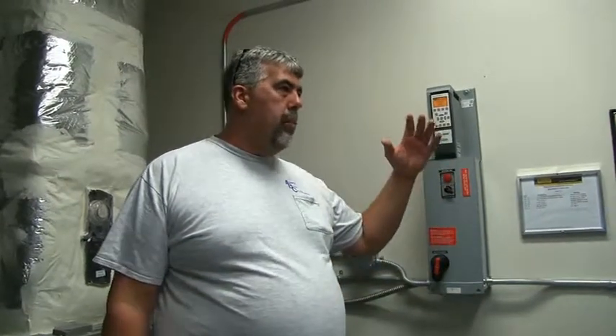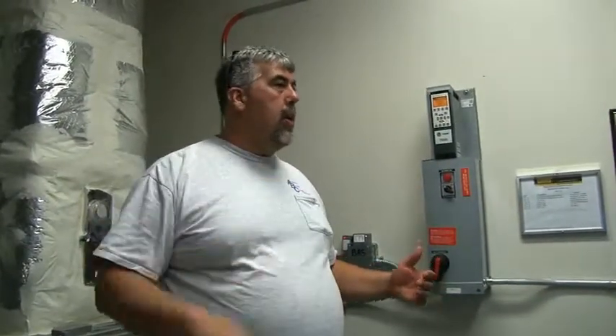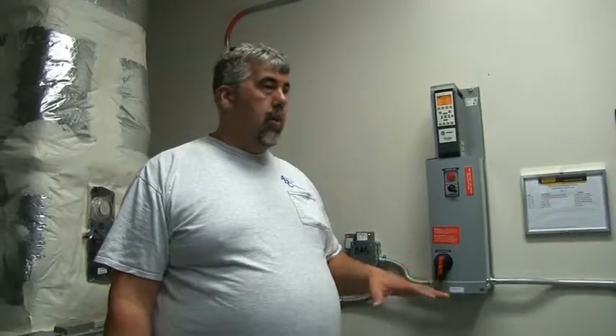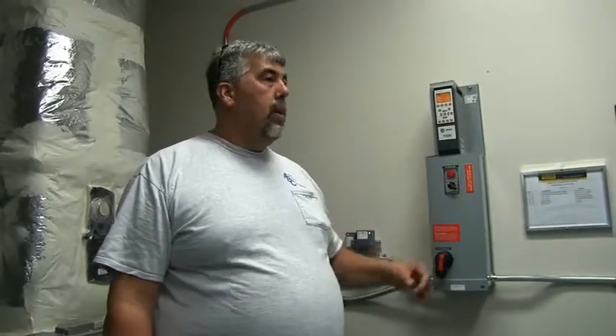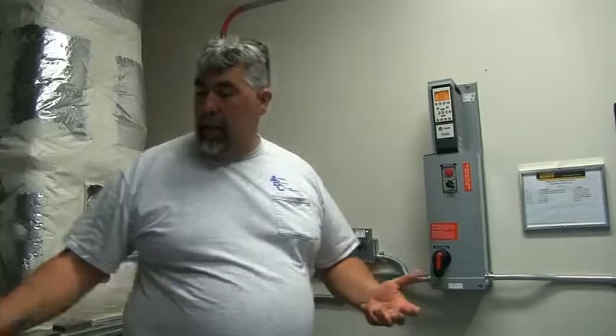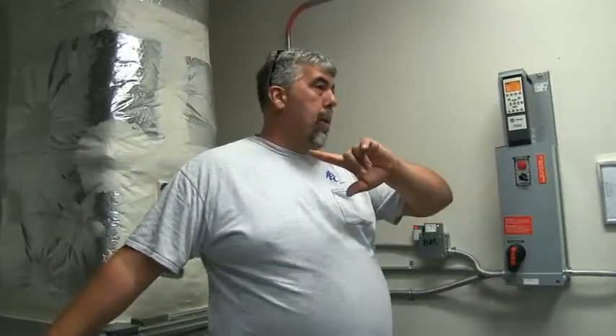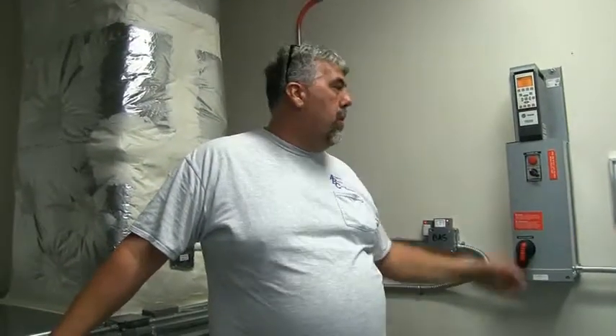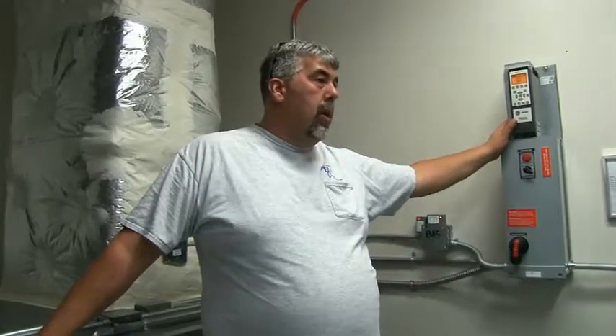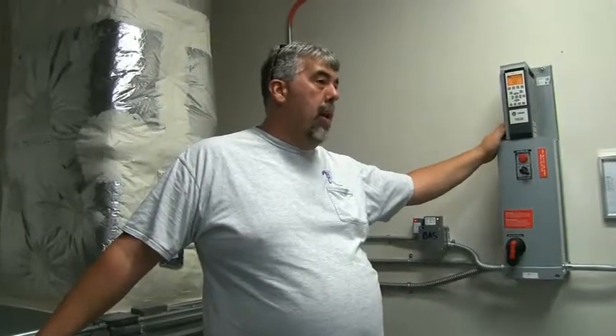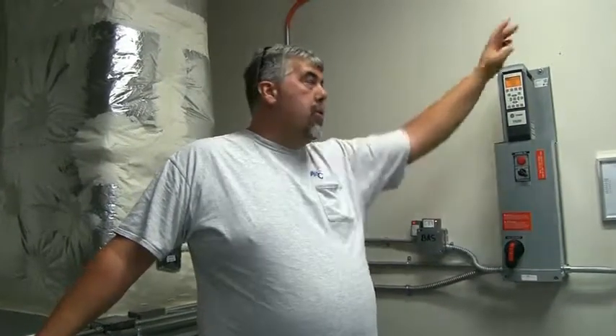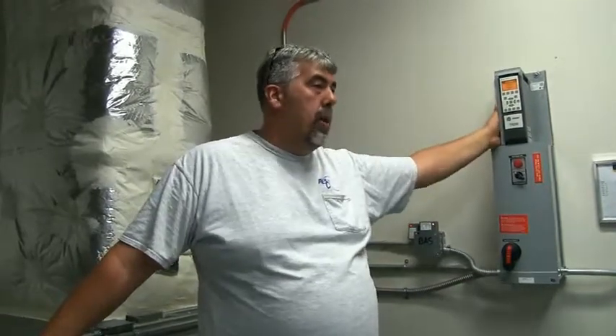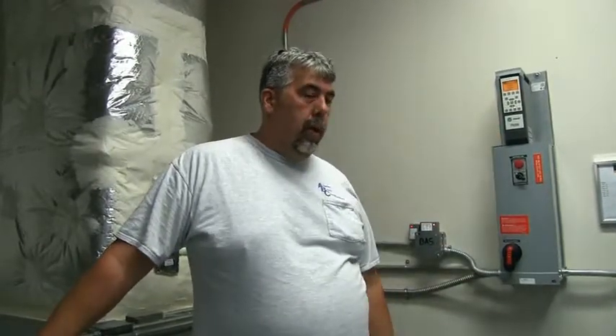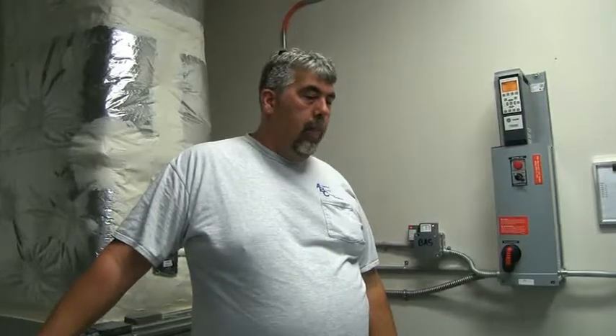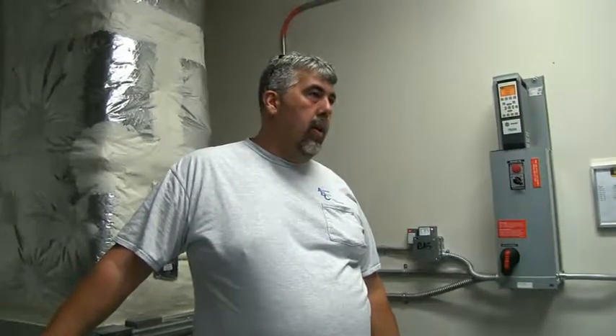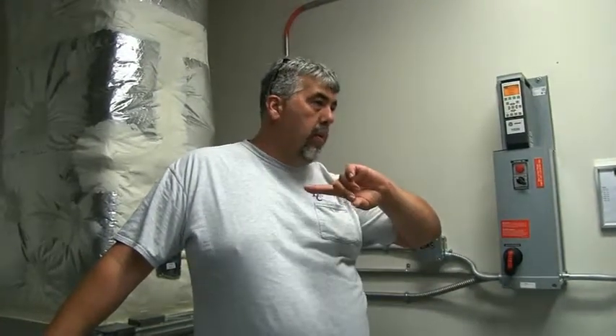I'm still shy a little bit. If the static pressure reset came down or whatever, then it'll start to look at that differently again. It'll start to adjust for that. But what I'm saying is, don't be alarmed at that being at 20% and that one being 100% open with the speed being low. Because that's just saying I need to have that much of my return closed off to force enough air through that outside air to make my set point. So, this one doesn't have a CO2 on it. The only one that has a CO2 on it is the cafeteria.